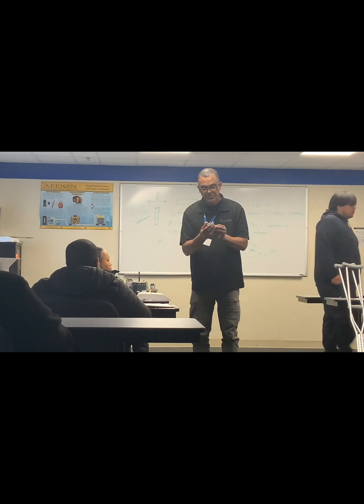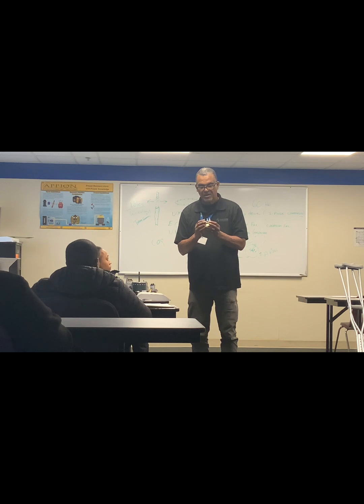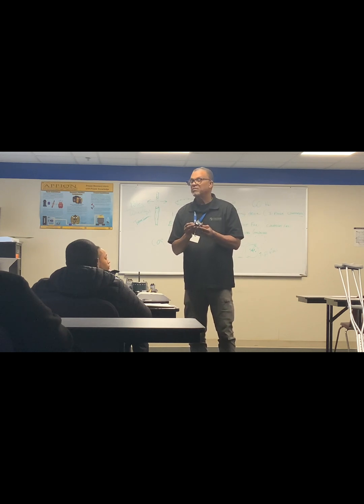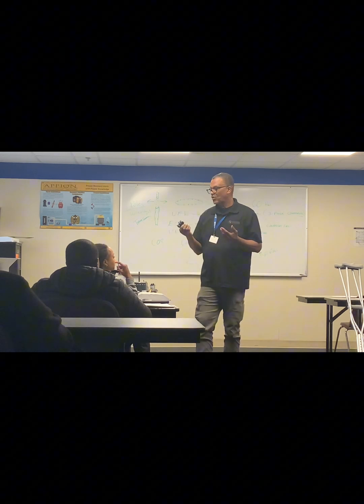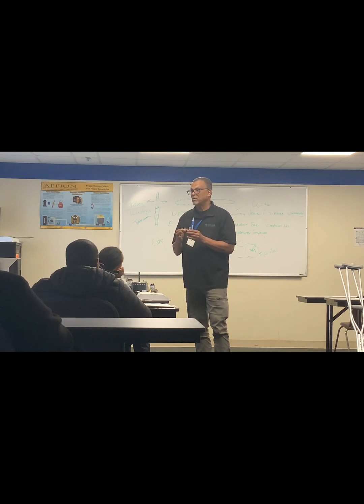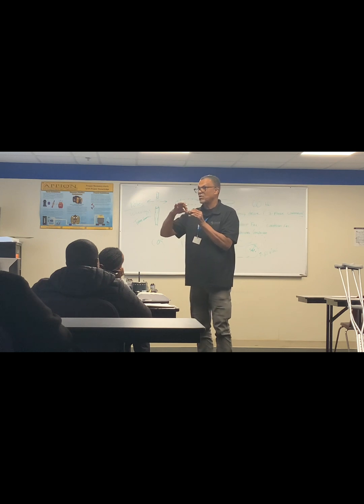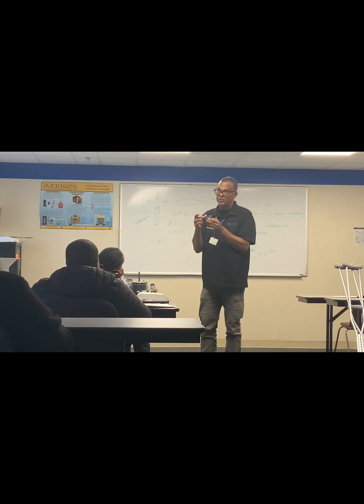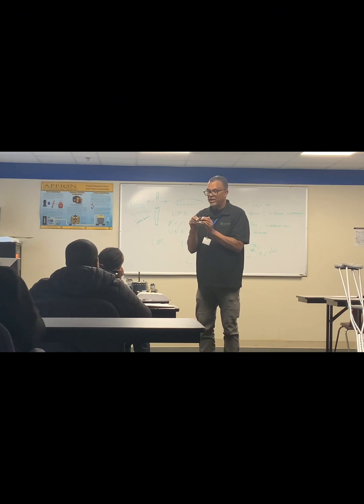1 and 3 for the coil, but that was a type of coil. What are we looking at? No, this is what I'm saying. If it says coil, then you look at where the coil is on the relay. And the coil would be here. Yeah, so this is the coil. And you can always check the coil by putting an ohm reading on it. So sometimes you don't have the exact replacement, but you can have the exact operation.